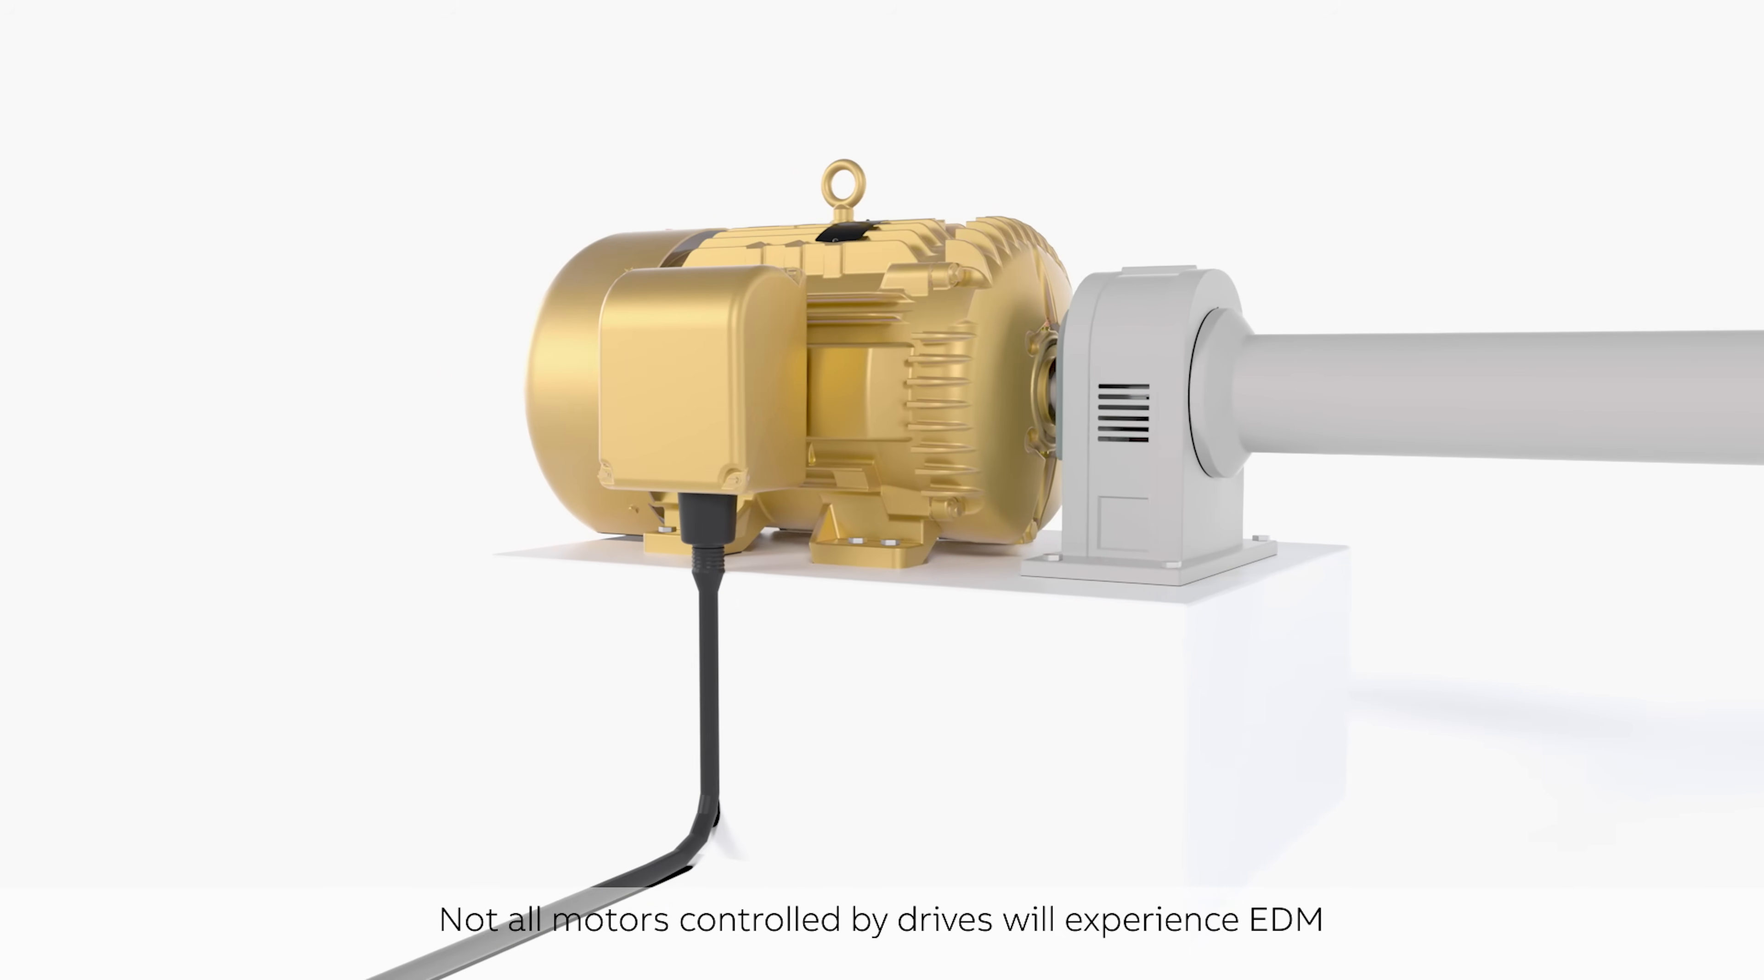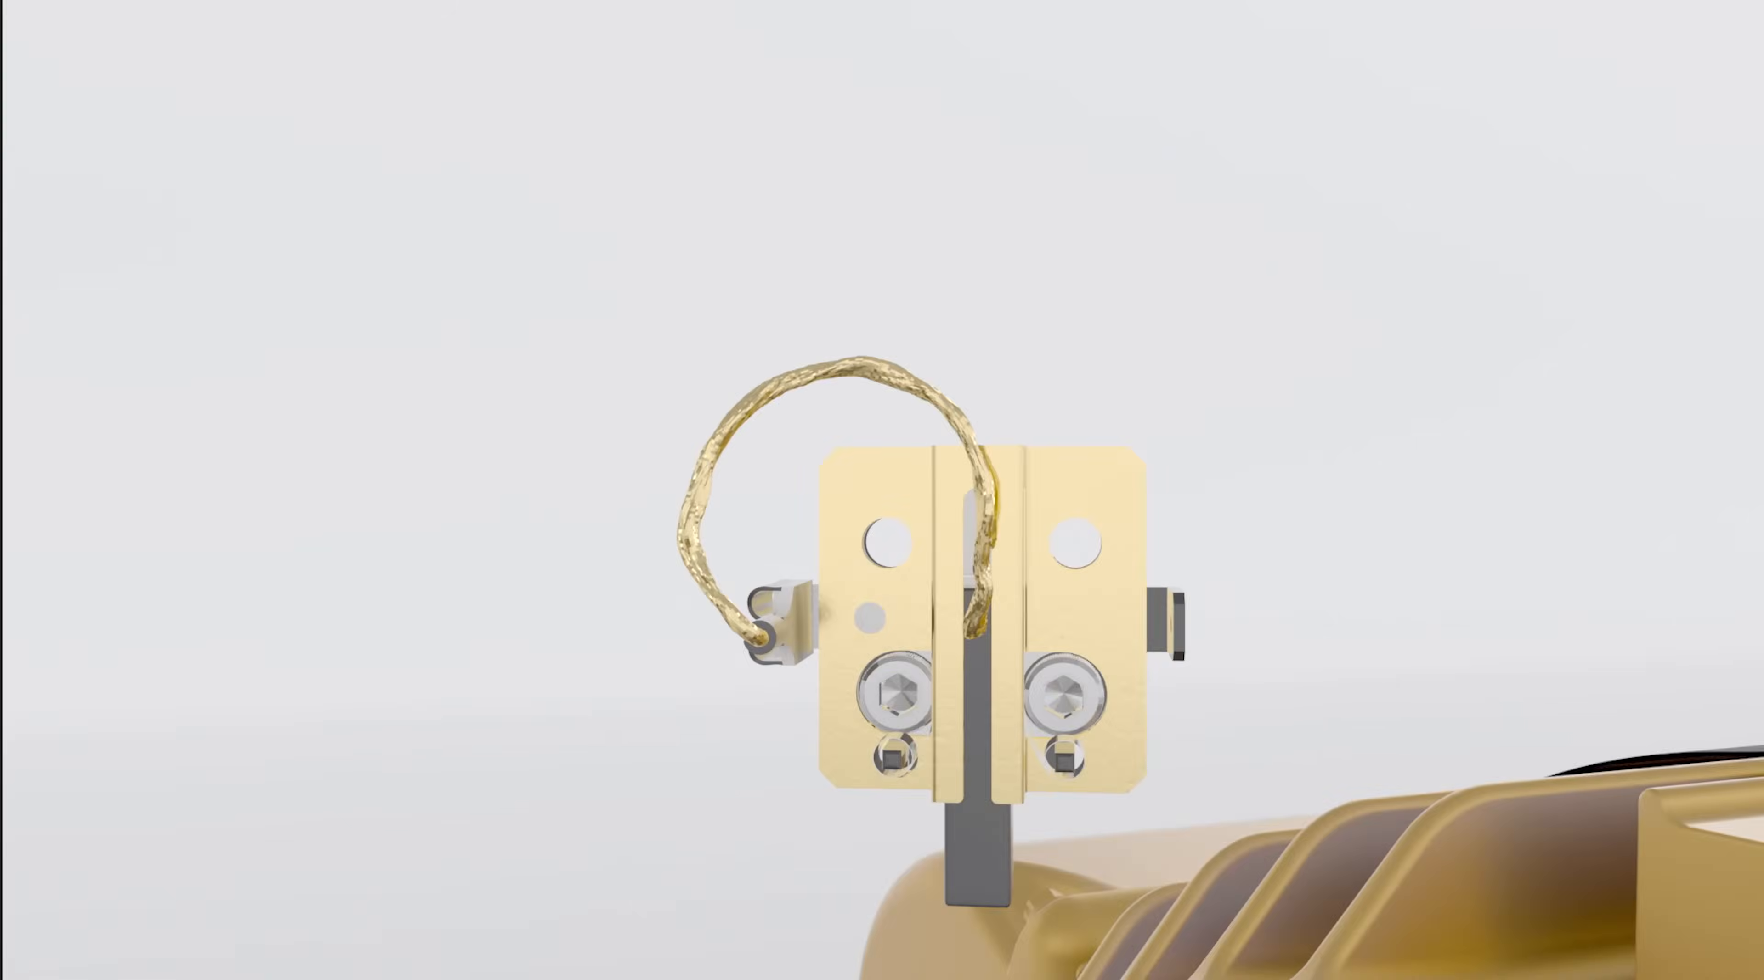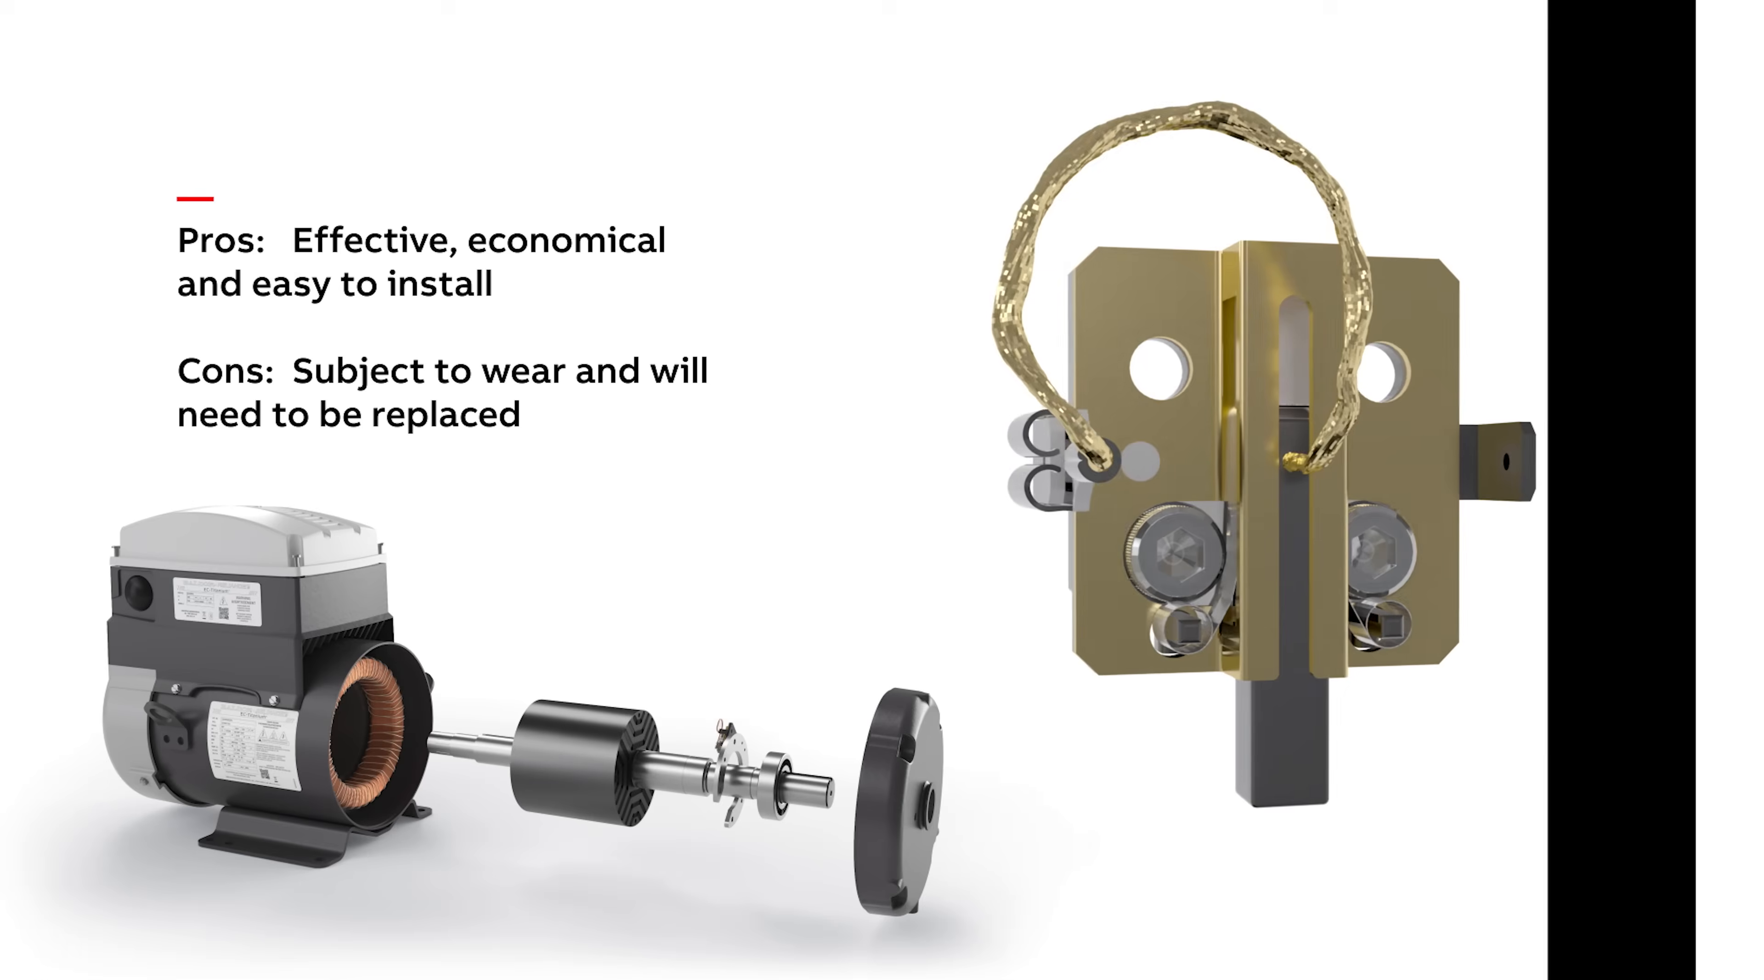Bearing protection from shaft currents can be done in a couple of ways. Shaft grounding brushes, similar to the carbon brushes used on DC motor commutators, have been in use for more than 100 years. Brushes provide a low impedance path from the rotor to ground so that the shaft voltage does not build up to the point where it discharges through the bearings. However, the brushes are subject to wear because of their contact with the shaft and will eventually need to be replaced.